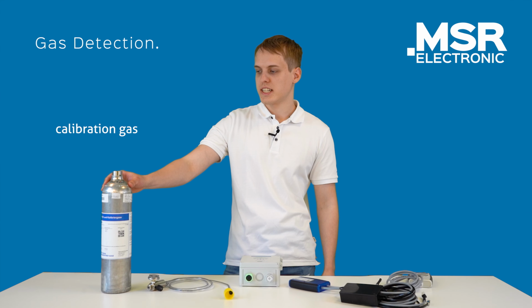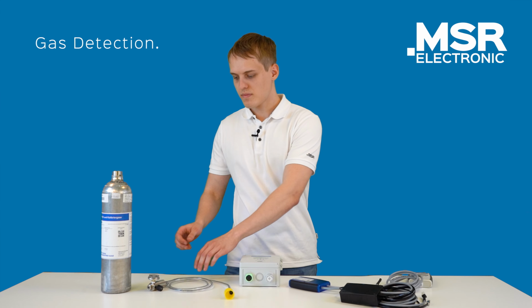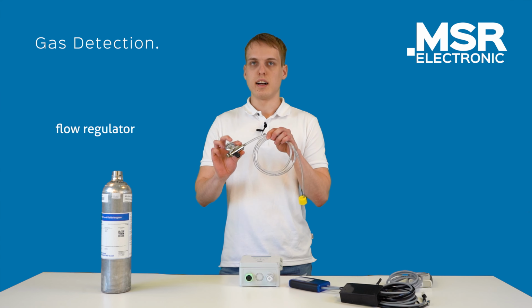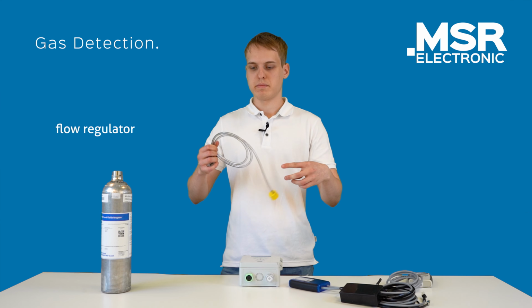For the calibration, you will need a calibration gas. Just make sure that the concentration is between 30 and 90% of the measuring range. Also, you will need a flow regulator, a hose and a sensor cap.